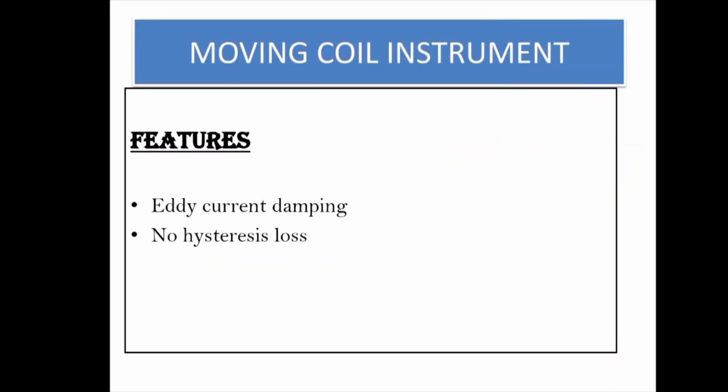Another feature is eddy current damping. The damping torque is provided by eddy currents induced in the metal former, which oppose the movement of the coil and reduce oscillations. Additionally, there is no hysteresis loss in these instruments.